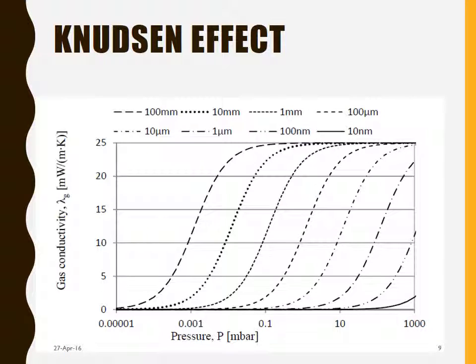This is a graph that shows how the gas conductivity changes with the pore size and the pressure. If we consider the rate of increase in pressure to be the same in all the materials, then as we decrease the pore size, the time required for the increase in gas conductivity also increases. That is, the service life increases as we decrease the pore size. As we enter into the nano range, the gas conductivity remains at its minimum till 10 millibars. Thus, it has a very large service life.